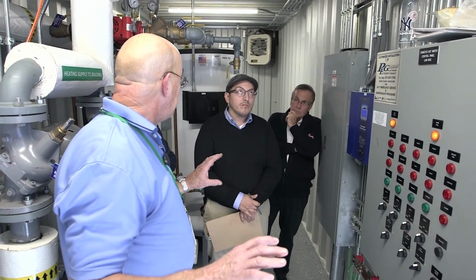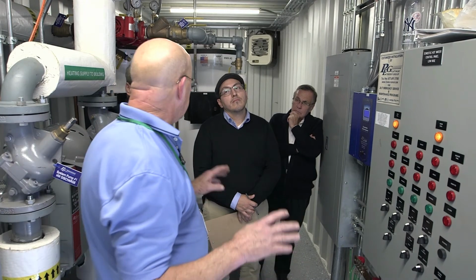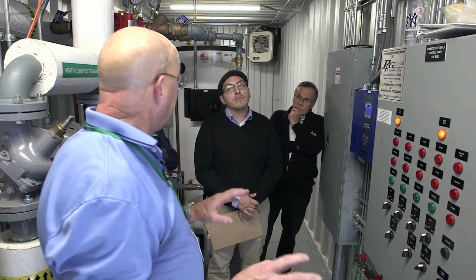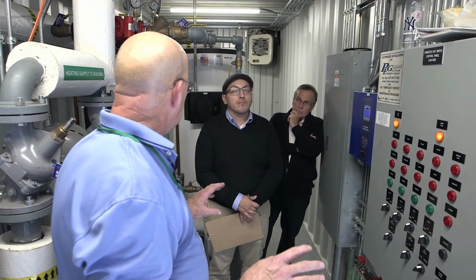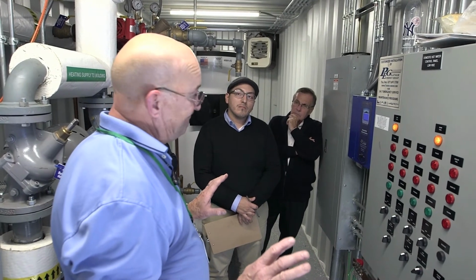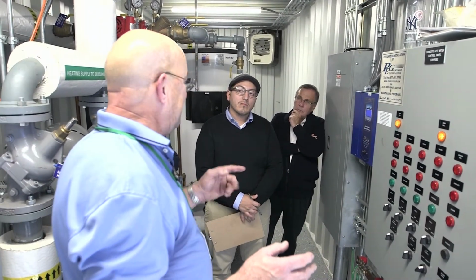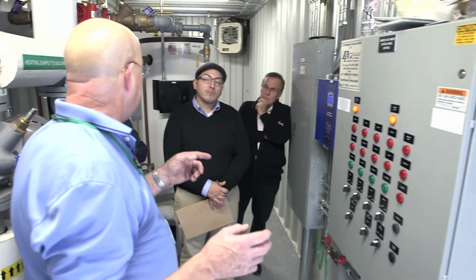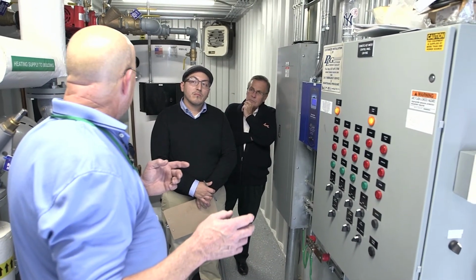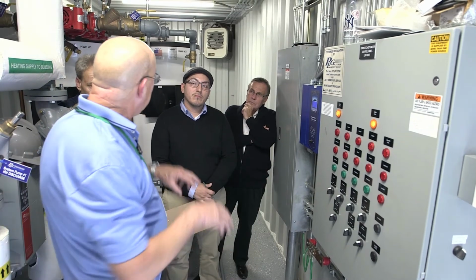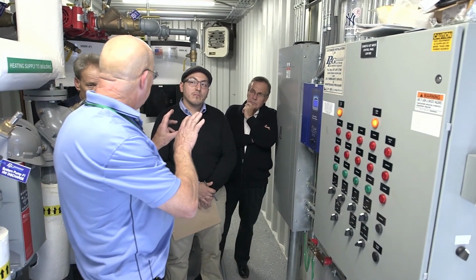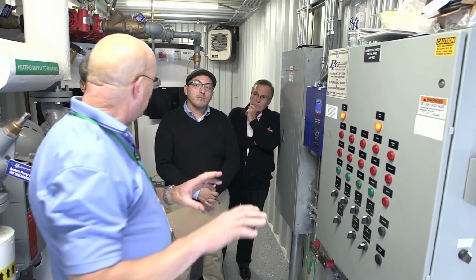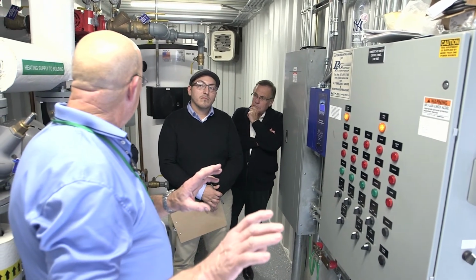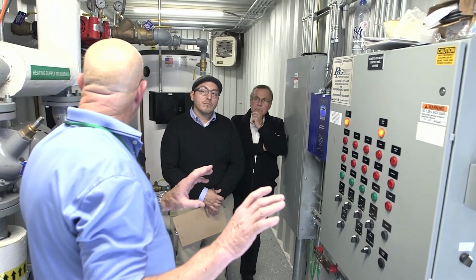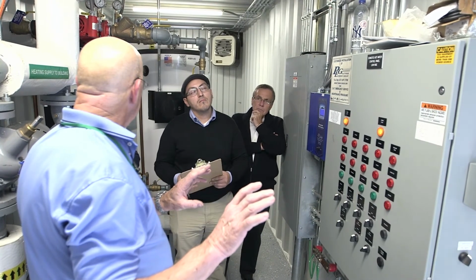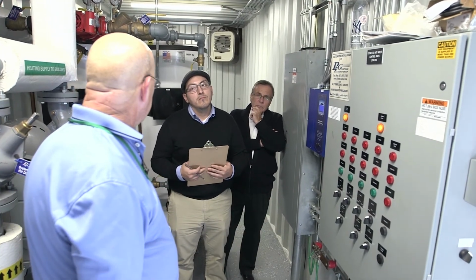It's taking an average. And what happens with that average, which is nice, is if you find you are overheating the building, you say to yourself, I can't believe these apartments are 62 degrees and all the rest is 70. You know what you're going to do? You're going to change the 10 sensors that determine it to different areas, and you're going to block those out. That's how you have maximum control over your building. It works out perfect that way.